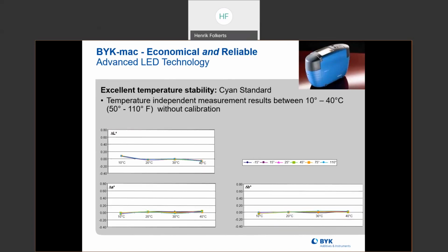And then maybe most importantly is that instrumentation stable over a wide temperature range? So temperature is something that we cannot control. Temperature will go up and down in our laboratories, not as much as in the plants and in the production environment, or whether you're using an instrument inside or outside. So this is really, really important to make sure that anything that you see in terms of your measurement differences is actually coming from the samples being different.